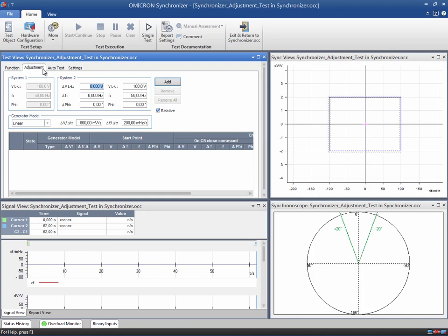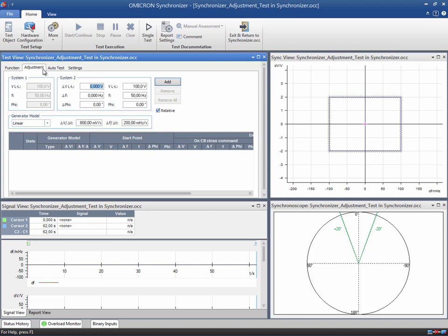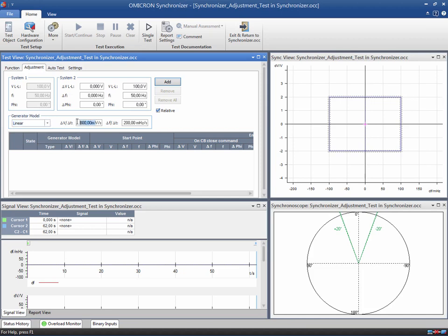At this point, we need to specify the mathematical model of the generator. It is used by the CMC to simulate the behavior of the generator when the relay issues actuator control commands. The synchronizer test module can work with predefined generator models or user-defined models. In this example, the generator follows a linear model. The voltage and frequency change ratios are 4 volts per second and 150 mHz per second.